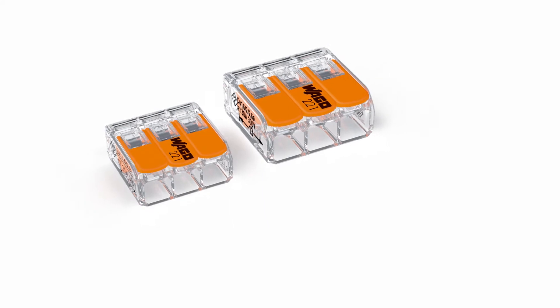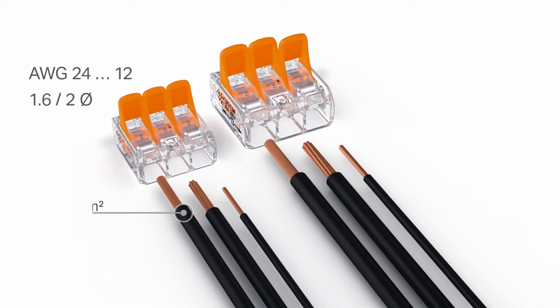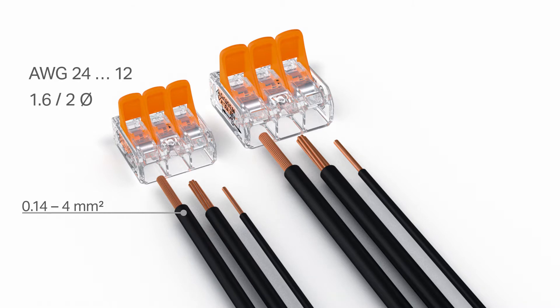The 4 square millimetre 32 amp version accommodates fine stranded conductors from 0.14 to 4 square millimetres, as well as solid and stranded conductors from 0.2 to 4 square millimetres.